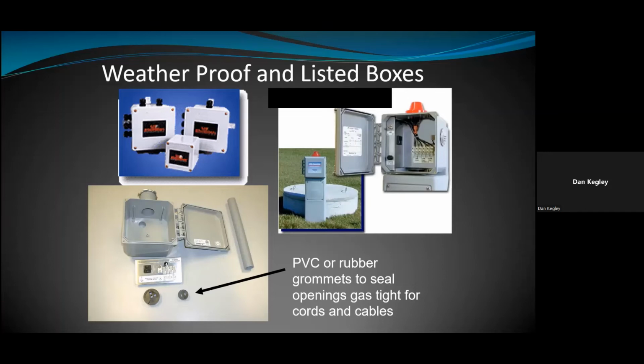For example, if you look at this picture in the bottom left-hand corner, that plastic box there has a big opening, probably going into the side of the tank, so the cords and plugs can fit through there. Let's assume the bottom is going down. It depends on the configuration, but there are no holes in this particular plastic box anywhere other than the main conduit holes, and those conduit holes will be sealed up anyway. So there's really no place for the moisture to go once it condenses and builds up in there. So some do, some don't. Unfortunately, it's not a plain yes or no answer. Yeah, sure. That's it for now. Okay.